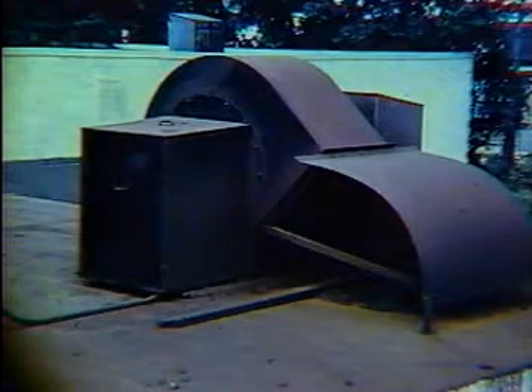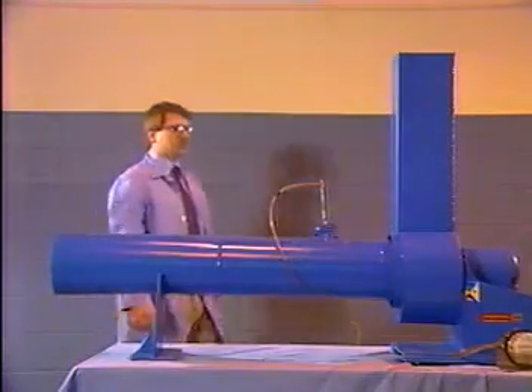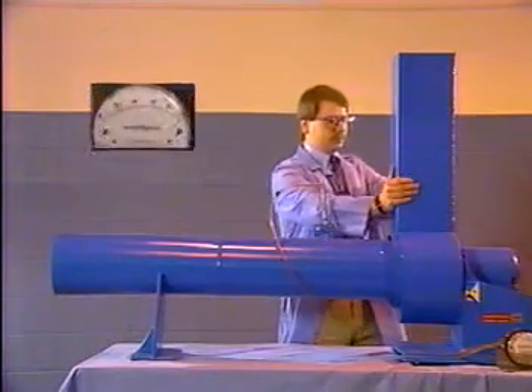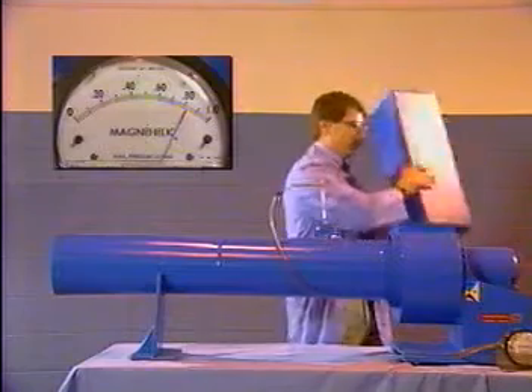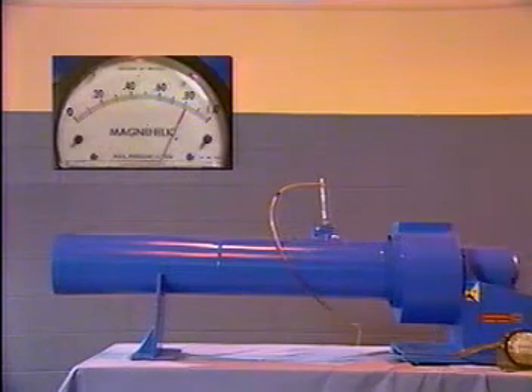The fan inlet is just half the story. The other half of the story is the fan outlet. The transition made at the fan outlet affects fan performance as surely as the transition at the fan inlet. Fans are tested with straight outlet ductwork. Unless your installation includes a straight run of ductwork at the fan outlet, the fan cannot operate at its full tested capacity. When there is no outlet duct, air can't discharge with even velocity.